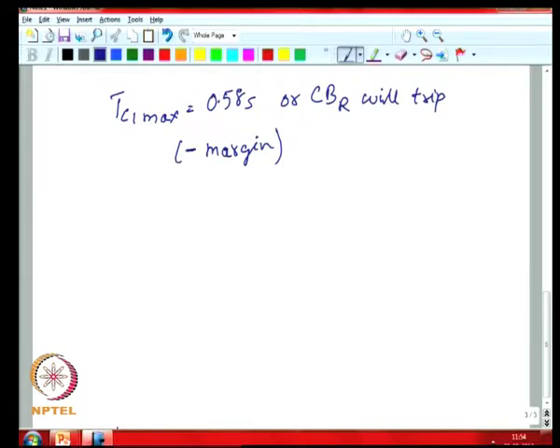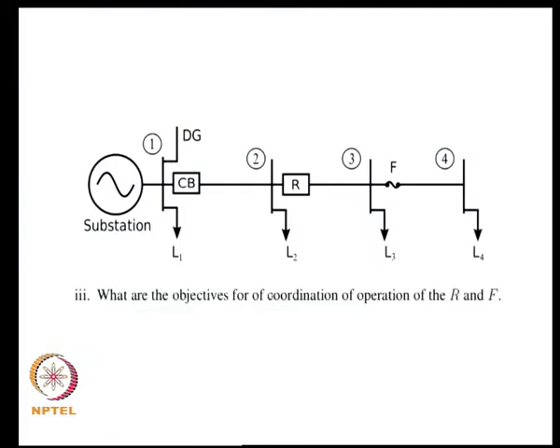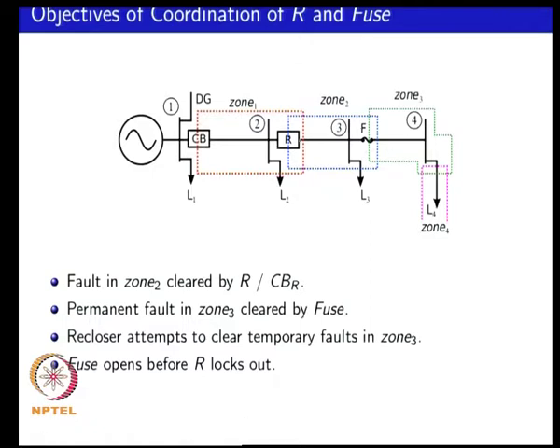The next problem is to look at the objectives of coordination of the recloser and the downstream fuse. If you have a fault in zone 2, it has to be cleared by the recloser or its underlying circuit breaker. If you have a permanent fault in zone 3, it has to be cleared by the fuse. Whereas if you have a temporary fault in zone 3, the recloser attempts to clear it, but before the recloser locks out the fuse has to blow. This is the requirement for coordination between the recloser and the downstream fuse.